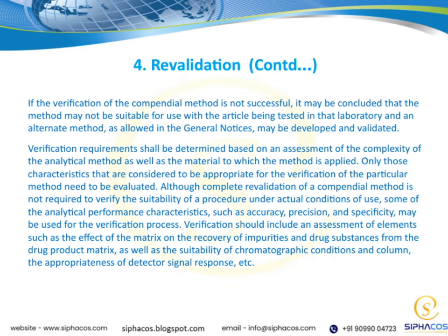Verification requirements should be tailored based on an assessment of the method's complexity and the material to which it's applied. Only those characteristics that are relevant and appropriate for verifying the particular method need to be evaluated. It's important to note that full revalidation of the original compendial method is not usually necessary just to verify its suitability under actual testing conditions. However, some key analytical performance characteristics like accuracy, precision, and specificity can be used during the verification process.